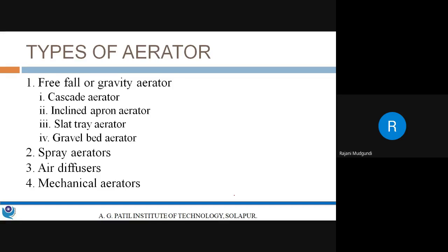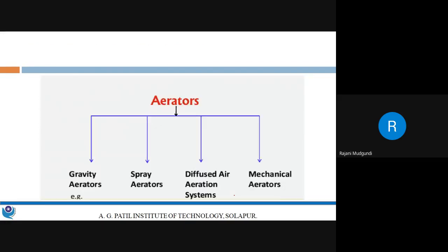There are various types of aerators. The classification includes: free fall or gravity type aerators, in which water is allowed to fall or flow under gravity; spray aerators, in which water is brought in contact with air in the form of spray; air diffusers, in which diffusers at the bottom of the aeration tank add air into the water; and mechanical aerators, which act as surface aerators.